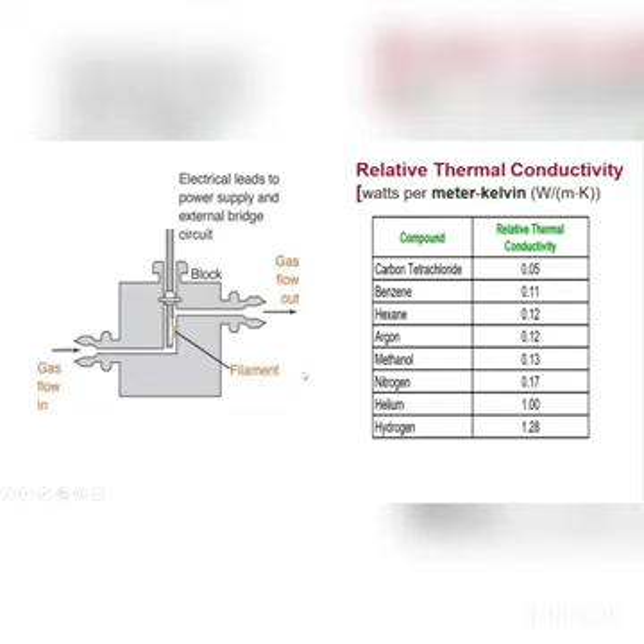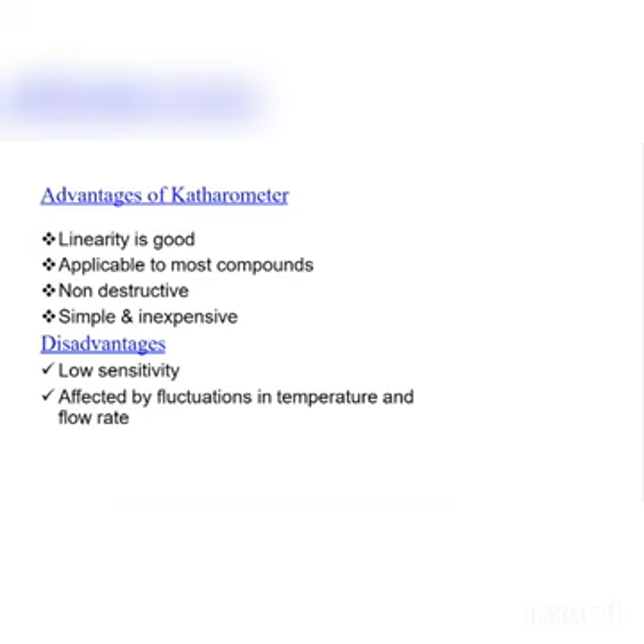The advantages of the catharometer are that the linearity is good. It is applicable to most of the compounds. It is non-destructive, simple and inexpensive. But the disadvantages of this detector are that it has low sensitivity and is affected by fluctuations in temperature and flow rate.